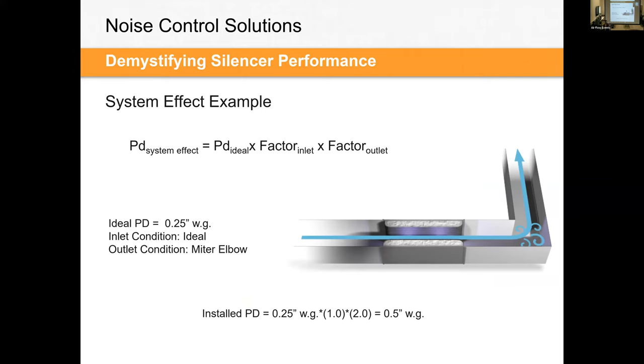ideal. What we do is often apply system effects, and I showed the software earlier, and this is how that usually works. When you have a pressure drop with system effect, you take your ideal catalog pressure drop and you apply a factor at both the inlet and the outlet. In this case here, if this silencer was installed in this orientation, our ideal silencer pressure drop of this device would be 0.25 inches of water gauge. On the inlet side, we'd have what we call ideal, a nice long straight run of duct going in. On the outlet, we have this mitered elbow. And the combination of those two conditions basically yields the inlet would be a 1.0 factor. The outlet would be a 2.0 factor, basically doubling the pressure drop to give us 0.5 inches of water gauge.